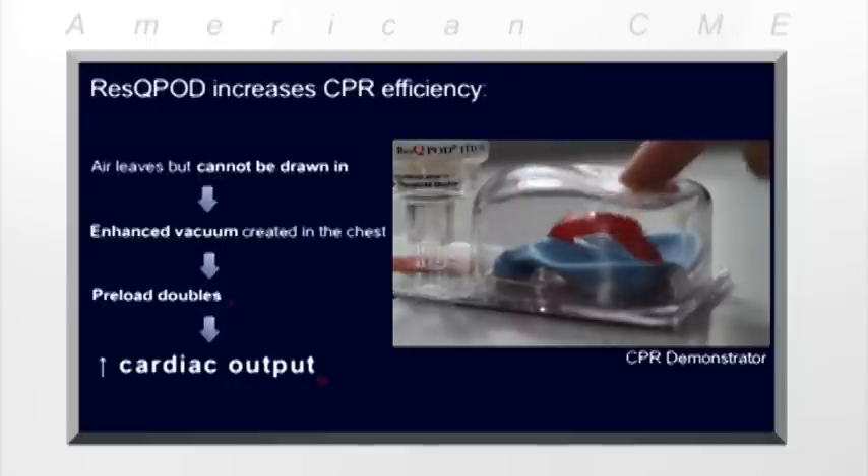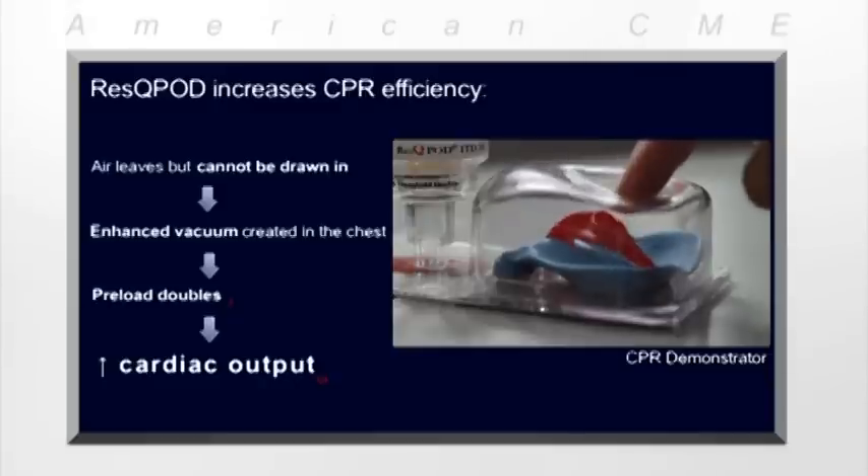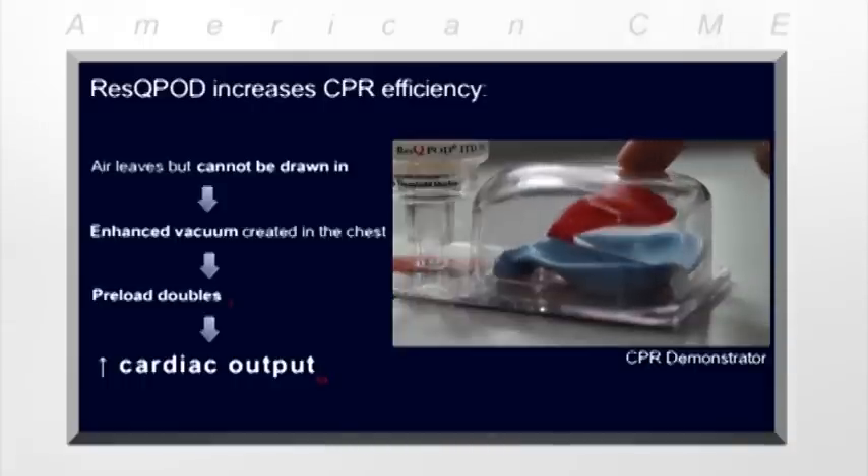The ResQPOD ITD corrects this problem. It's attached to a face mask or other airway device and regulates the flow of air into the chest during CPR. When we push down on the chest, air can freely leave the patient. But as the chest wall recoils, the ITD closes and prevents air from being drawn back in. This creates a greater vacuum in the chest, pulling twice as much blood back to the heart and circulating that blood forward on the next compression.